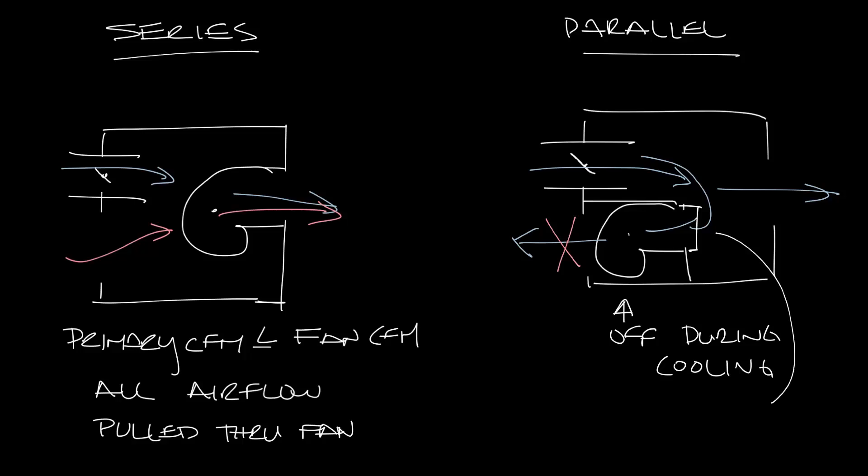So that's where the backdraft damper comes in. There'll be a backdraft damper at the discharge of the fan to prevent the air from coming in the primary and out through the induced air inlet.